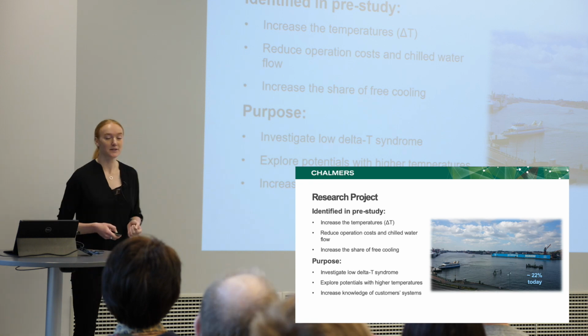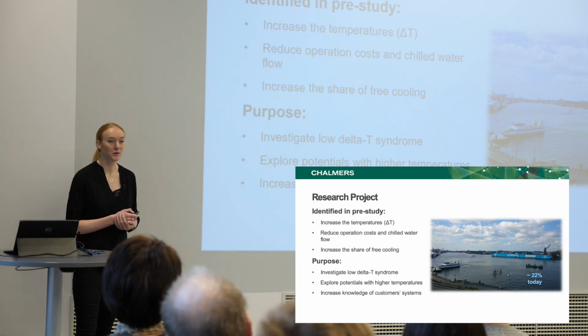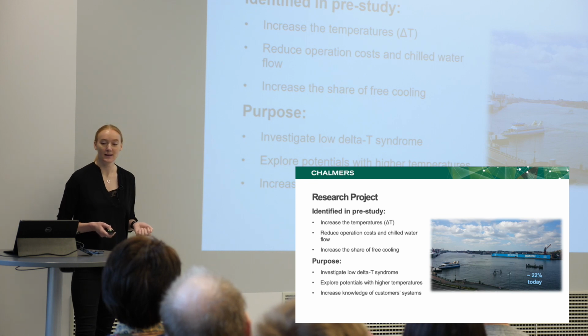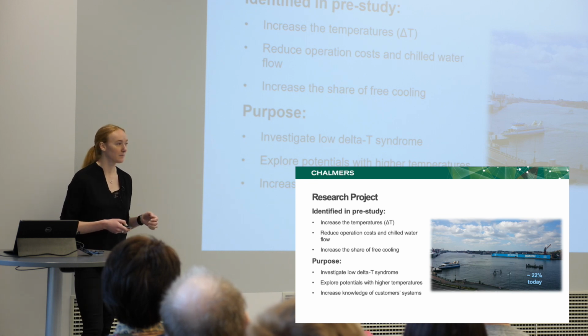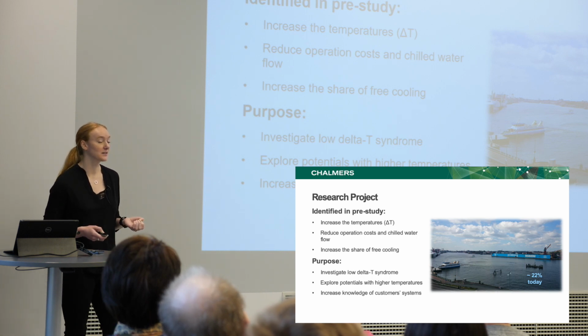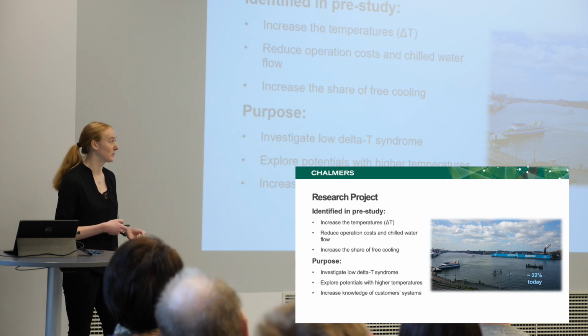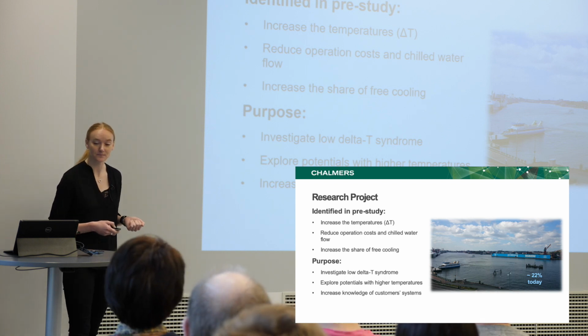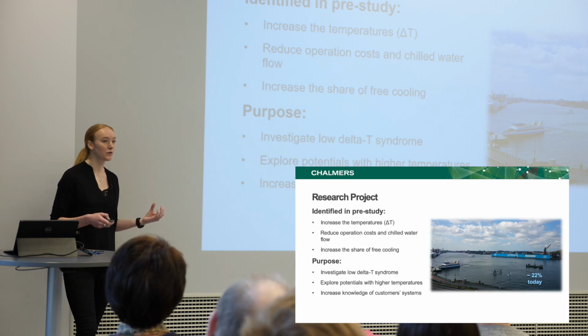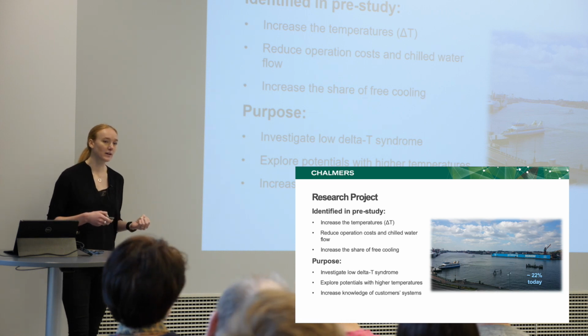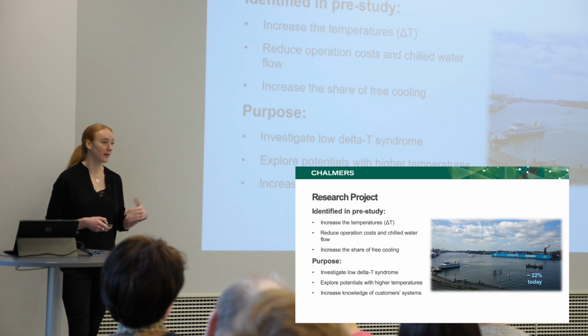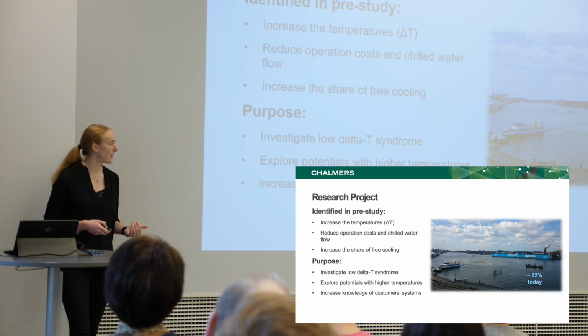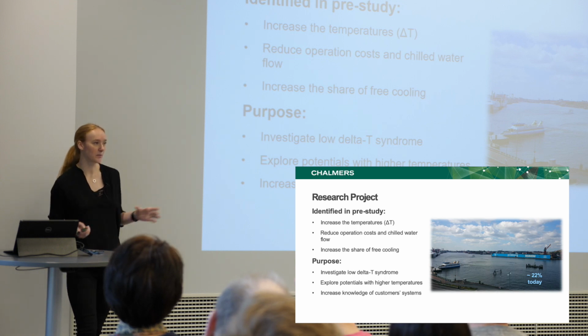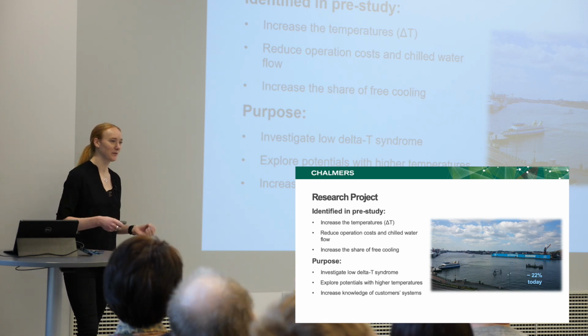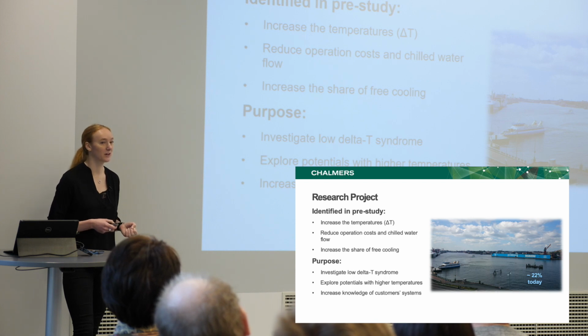So the purpose of my research project is to investigate the low delta T syndrome, what can be done to increase the temperatures, and then also explore the potential to be using even higher temperatures than the 6 degrees supply and 16 degrees return, because then the share of free cooling can go up even higher, as you will soon see. And this is an approach from the customer side. So the utility company has quite little knowledge of what's going on the other side of the heat exchanger. So that's where my research project is approaching this issue from their point of view, by increasing the knowledge of the connected customers.